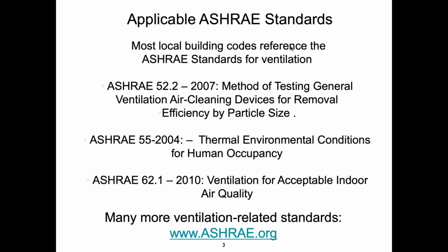There are organizations that have some standards, though. One of the major ones is ASHRAE, the American Society of Heating, Refrigerating and Air-Conditioning Engineers. They have three important standards related to indoor air quality, particularly in commercial office buildings. One of them is ASHRAE Standard 62, which determines how much exchange with outside air you need to keep people comfortable and to control odors and contaminants in indoor air. That's literally how much fresh air we have to get into a building as air is recirculated to keep things comfortable. We're going to be talking about that quite a bit more.